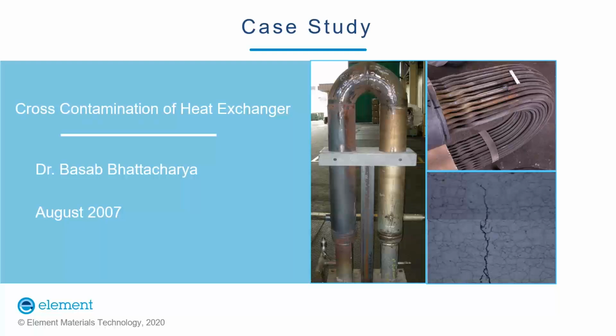As per client supplied information, the temperature of the superheated steam at the inlet, which is also called the hot side, was supposed to be 500 degrees Celsius. The heat exchanger was operating at a pressure of 150 psi. The purpose of this study was to determine the root cause of this failure. The case study was conducted at our Singapore facility. As mentioned by our previous speaker, we have tried to keep the content as simple as we could so that the presentation remains interesting to all of our audience.